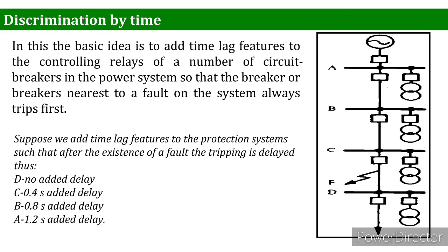The first method is discrimination by time. In this method, the basic idea is to add a time lag feature to the controlling relays of a number of circuit breakers in the power system. The reason is so that the breaker nearest to a fault on the system always trips first, as timing is very important in any protection system.